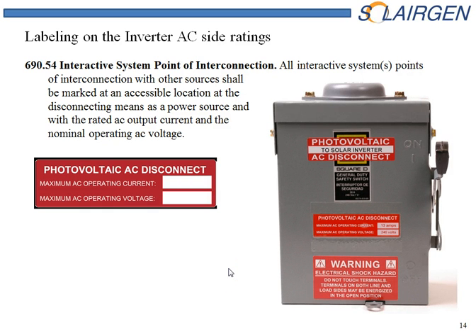AC disconnect labels. So the AC disconnect must be in a readily accessible location. Believe it or not, inside of a home, as long as it's readily accessible, is considered readily accessible. Now the utility company won't recognize that. They will insist that it be placed outside where it should be. So more than likely this is where you place it. Not only does it have to say AC disconnect, but it also needs to state the operating voltage and the operating current.